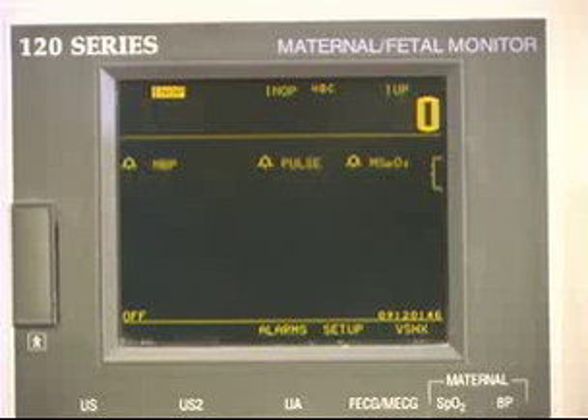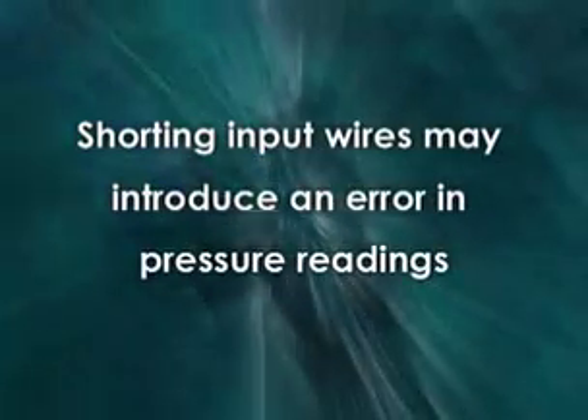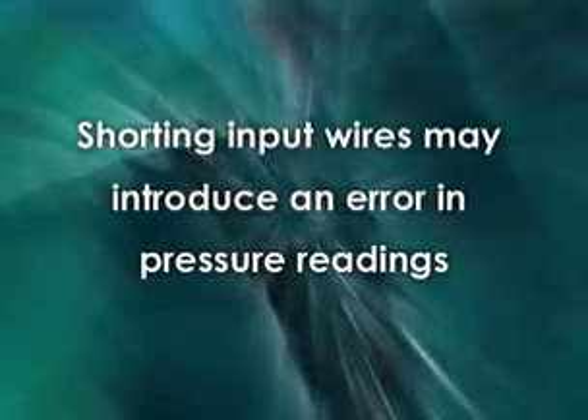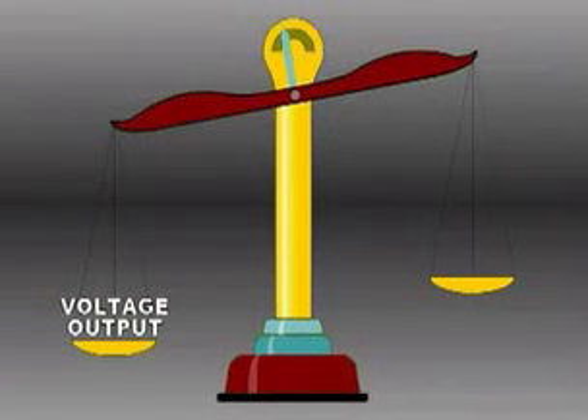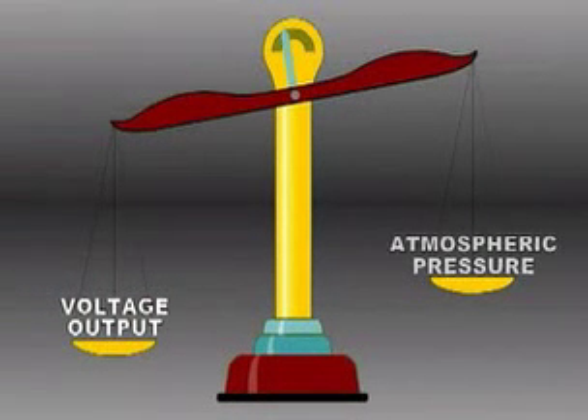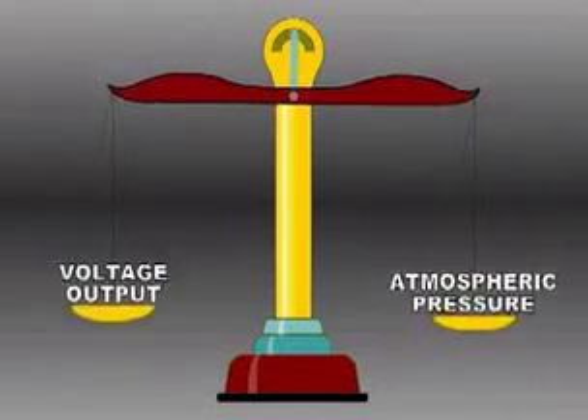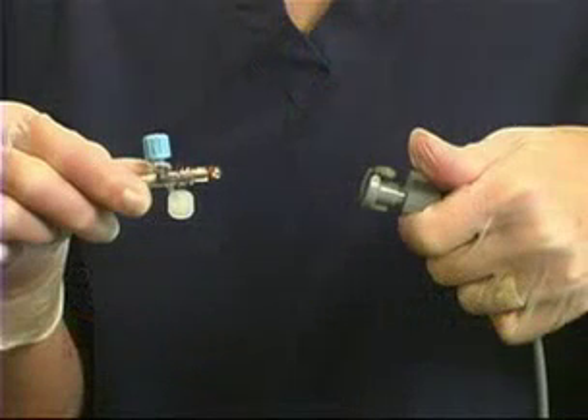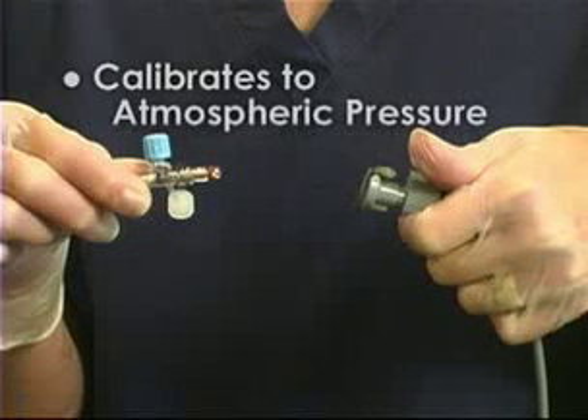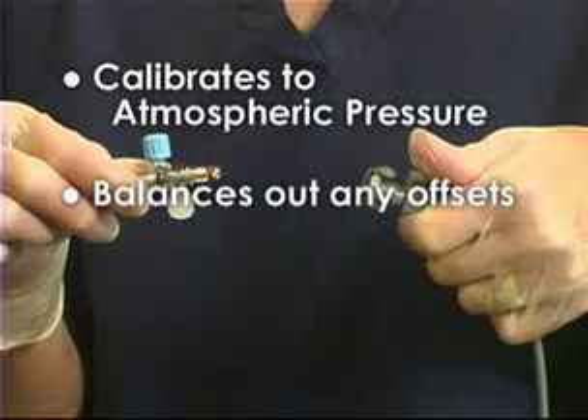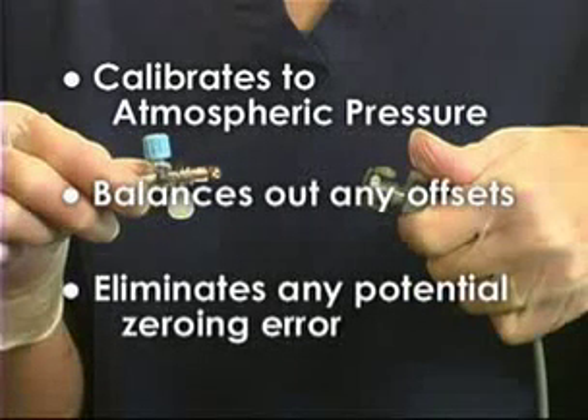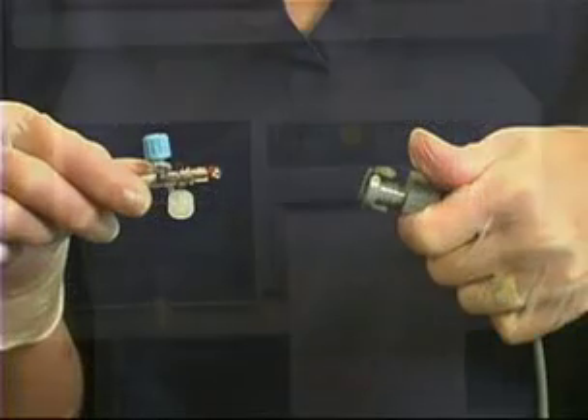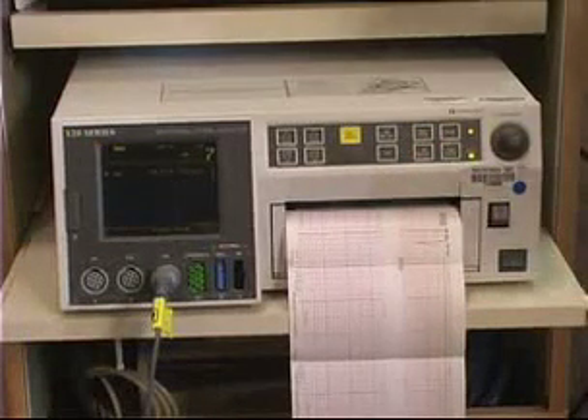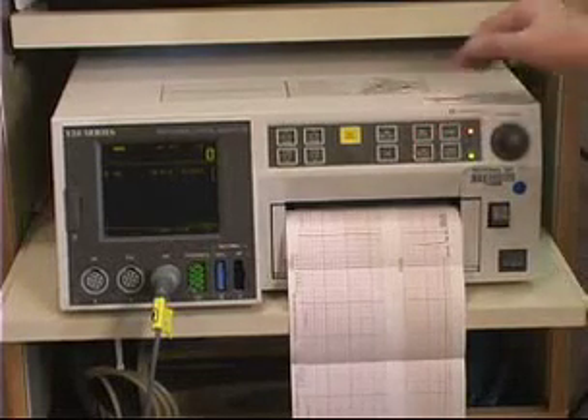If transducer-tipped catheter settings are inaccurate, or if the transducer has malfunctioned since production, then shorting the input wires may introduce an error into the pressure readings. The only way to have a true zero in utero is to have the transducer exposed to atmospheric pressure when the monitor is zeroed. Because its transducer is in the reusable cable rather than in the tip, the Koala calibrates to atmospheric pressure, balances out any offsets, and eliminates any potential zeroing error whenever it is disconnected from the cable. To zero the Koala pressure monitoring system, press the monitor's zero button while the catheter is disconnected from the reusable cable.